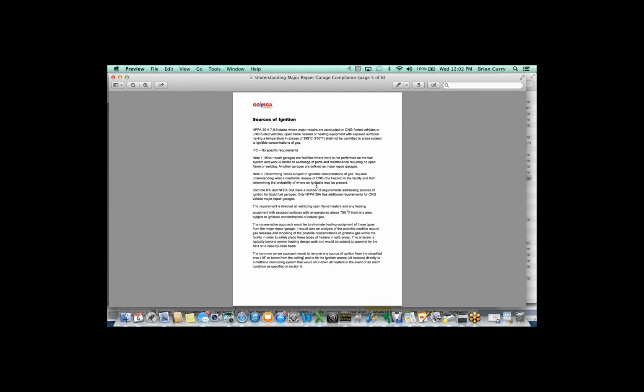Obviously, the easiest solution would be to change every single heater with an explosion-proof heater. You're probably not going to put radiant heat in the floors in an older building that's been built for 50 years. But if I were to design a new shop where I knew there were going to be CNG vehicles going into the shop, I would probably go with radiant heat. I've seen both, and again, it depends where it's at. But that's typically what we do.